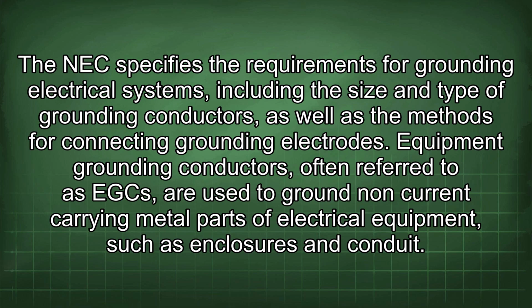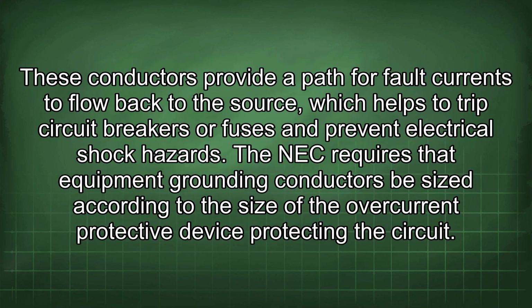Equipment grounding conductors, often referred to as EGC, are used to ground non-current carrying metal parts of electrical equipment, such as enclosures and conduit. These conductors provide a path for fault currents to flow back to the source, which helps to trip circuit breakers or fuses and prevent electrical shock hazards. The NEC requires that equipment grounding conductors be sized according to the size of the overcurrent protective device protecting the circuit.